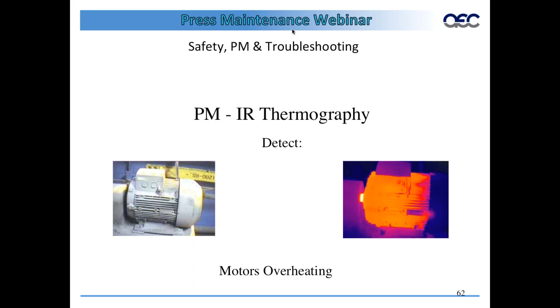Here's a motor that's overheating. When you look at the motor, you see the whole motor is hot. With the range of temperature that you set for it, you can see from white down to dark, you can set the range. So that doesn't mean it's extremely hot. It means it falls into the range that you set. The whiter, the lighter the color is, the hotter the source is. So this gives you a good indication here that the whole motor is hot.